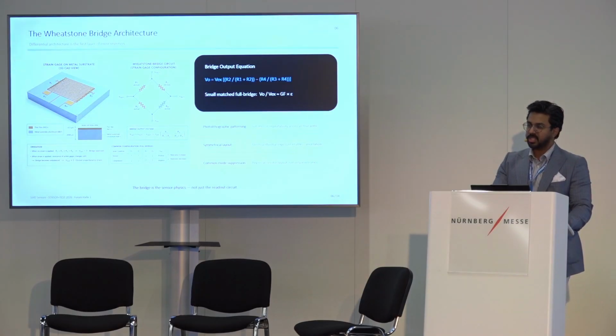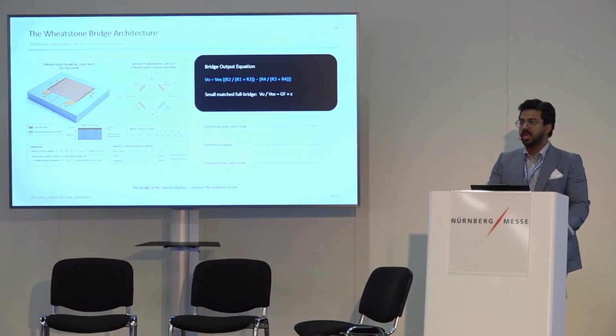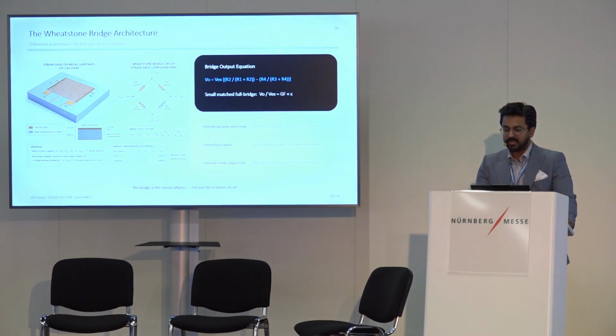But certain changes can create issues. For example, if the Wheatstone bridge gets hot, every resistor will see temperature changes. Theoretically, if they're changing temperature at the same rate, it cancels out. But as a sensor manufacturer, we also control the variability of these Wheatstone bridges, and we temperature-compensate for each of these pads as well. So there's some compensation that takes place, and we're aware of it before we even architect any software.